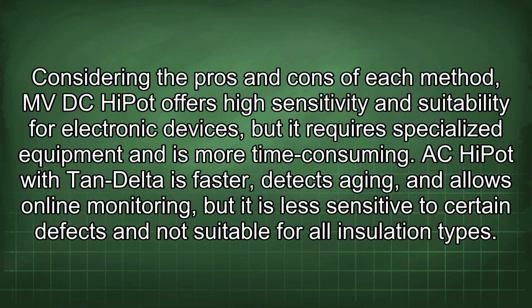Considering the pros and cons of each method, MVDC HiPot offers high sensitivity and suitability for electronic devices, but it requires specialized equipment and is more time-consuming. AC HiPot with tan delta is faster, detects aging, and allows online monitoring, but it is less sensitive to certain defects and not suitable for all insulation types.